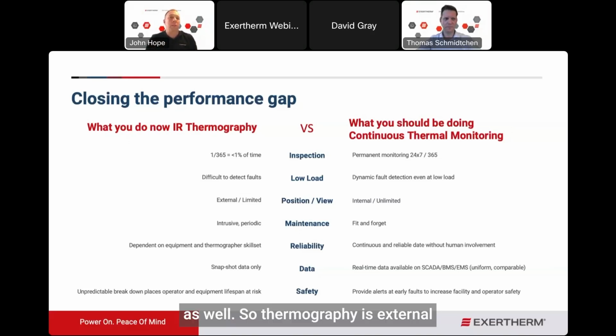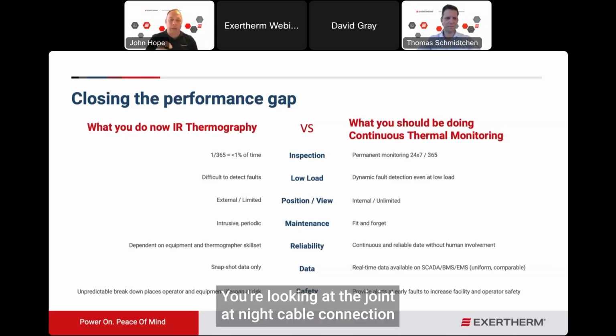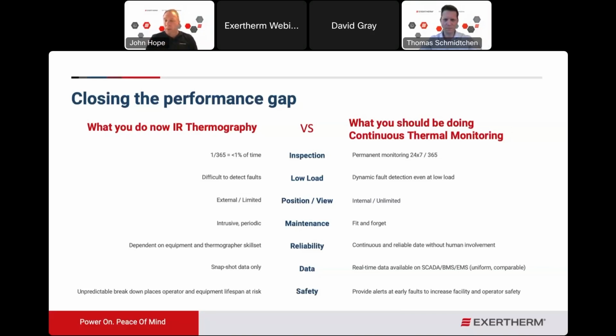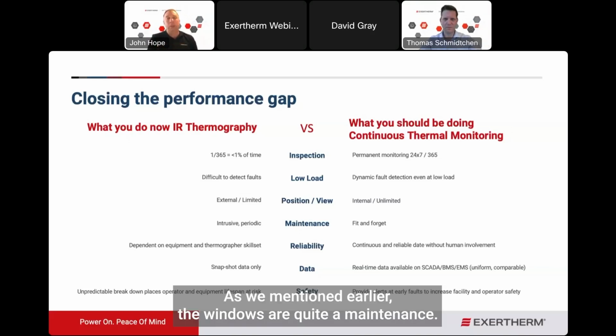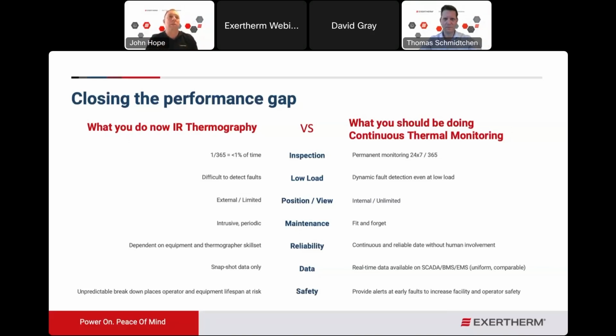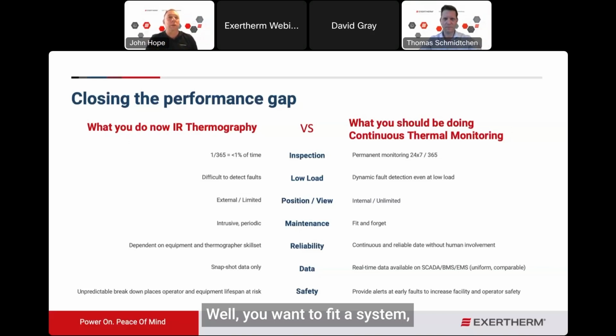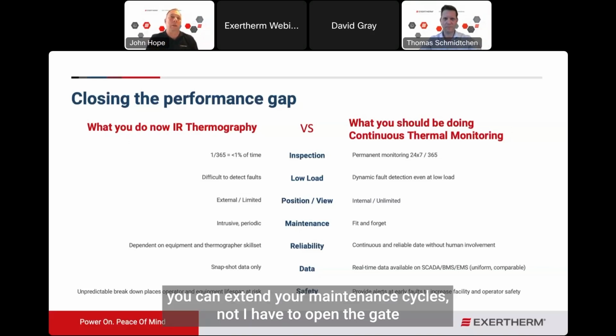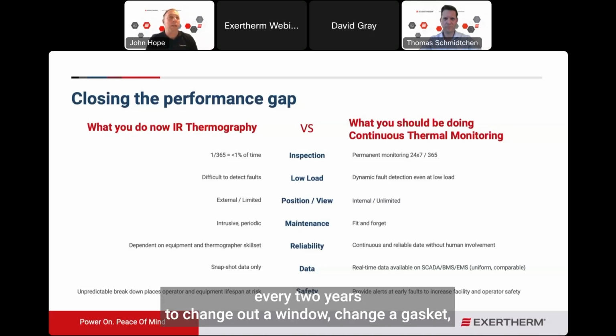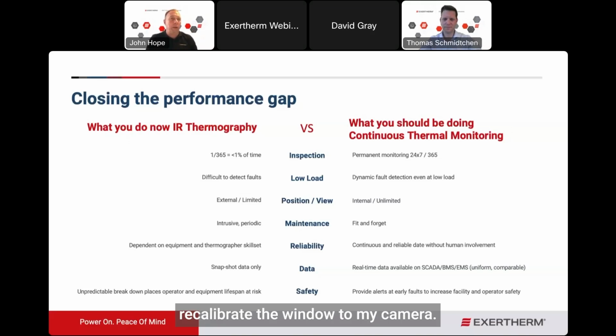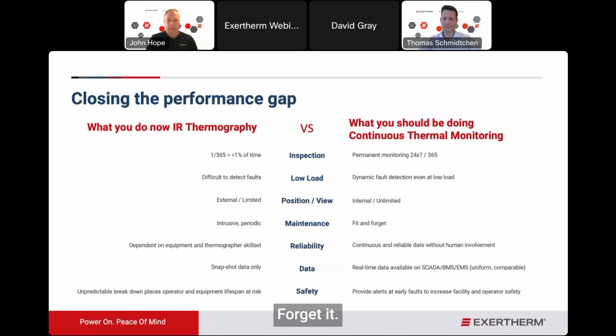As we said, thermography is external. Constant monitoring, your sensors are inside the gear. You're at the point of interest. You're looking at the joint, at that cable connection. And it's a fit and forget. There's no maintenance. As we mentioned earlier, those windows require maintenance. Well, if you fit a system, you can extend your maintenance cycles. Not, I have to open the gear every 2 years to change out a window, change a gasket, recalibrate the window to my camera. No, leave it closed. It's fit and forget.